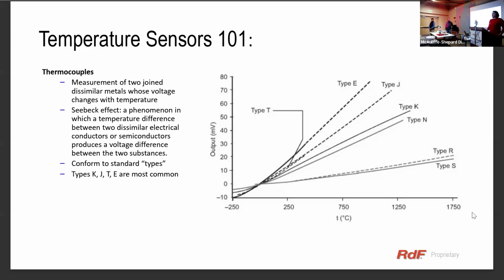And it will depend on which materials you chose to join. For that reason, thermocouples always conform to a standard type. These are agreed internationally. Very common types are K, J, T, and E. We've got a few of them plotted on this graph, so you can see that over a temperature span of minus 250°C up to 1750°C, they each perform differently, giving a different millivolt output depending on the temperature. So that's basically what a thermocouple is.